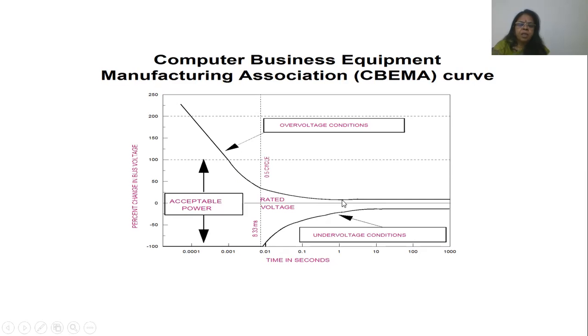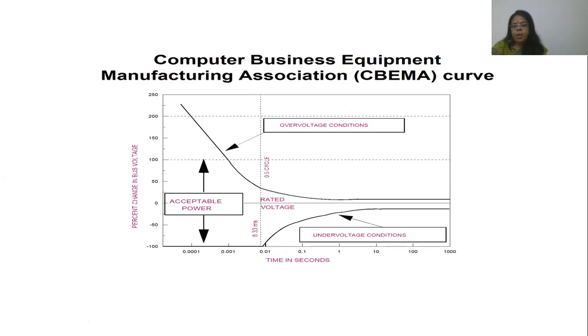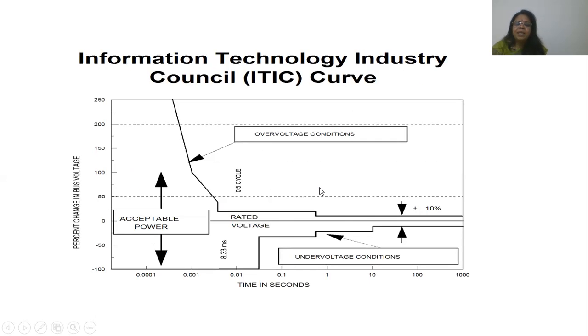These boundaries tell us: larger magnitudes the equipment can withstand only for a shorter time; smaller magnitudes it can withstand for a longer time. Above the upper boundary is an over voltage condition; below the lower boundary is an under voltage condition (sag or swell for short durations). The ITIC curve is similar but uses straight lines instead of curves. Anything within the boundary is acceptable; anything outside is non-acceptable.